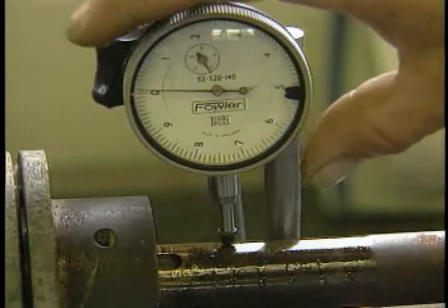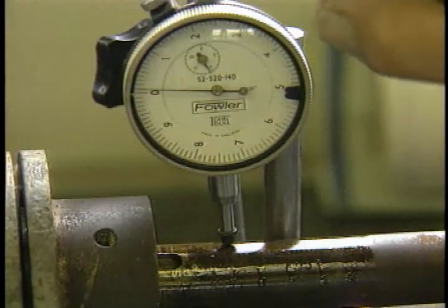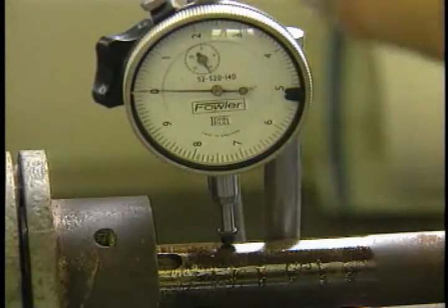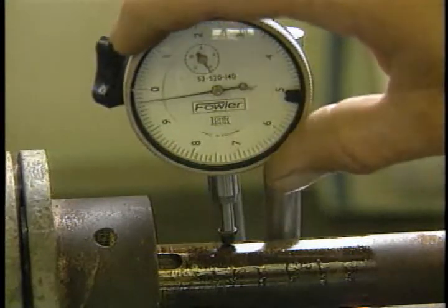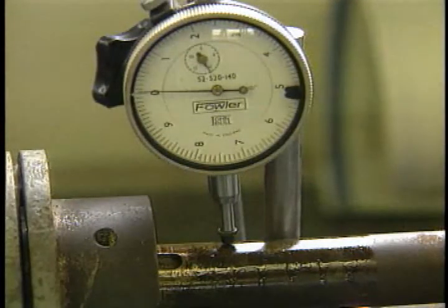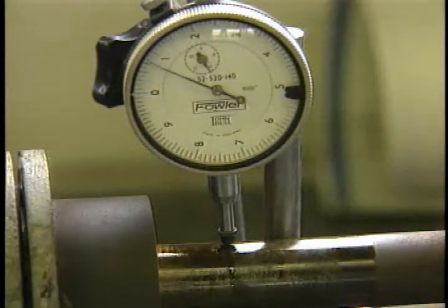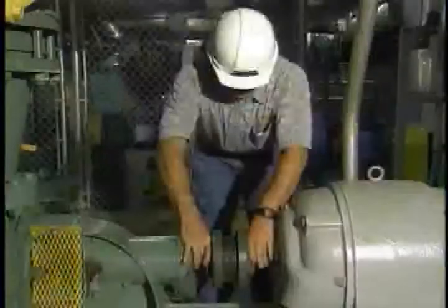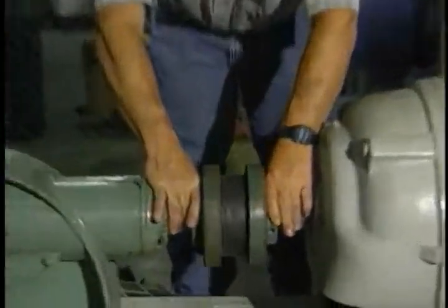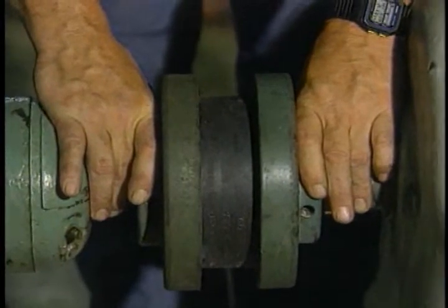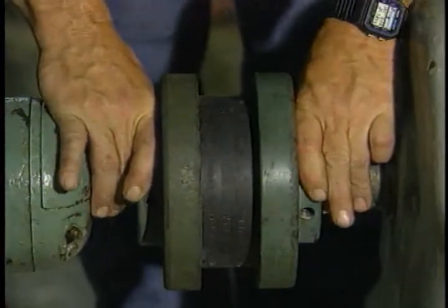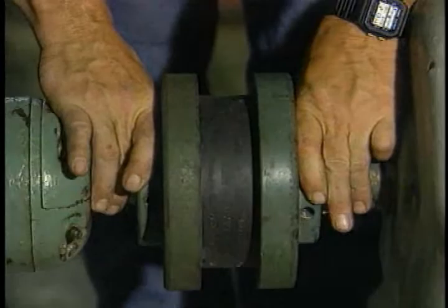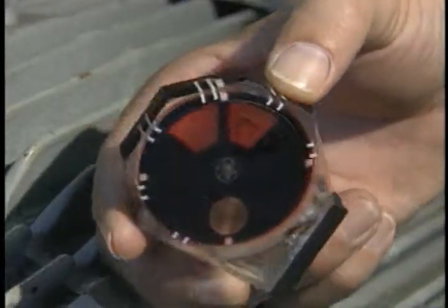Before beginning the alignment procedure, check the shafts to see if they are running true. This check can also be performed with a dial indicator. If either shaft is out of specification, it must be replaced. Finally, the coupling should be checked for slack or backlash. If slack exists in the coupling, measurements may not be correct. If the slack cannot be removed, 2 inclinometers or the electronic equivalent must be used to ensure accurate alignment.